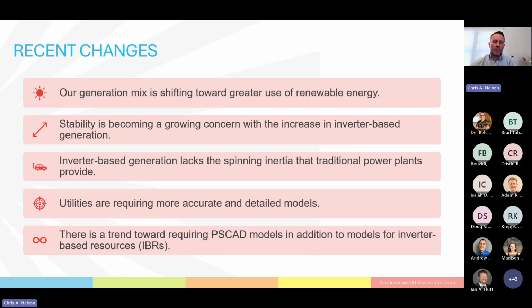So a conventional generator might provide 8 to 10 times the fault current of nominal if there's a problem, and it'll just continue spinning even if there's a little problem. Inverters might not do that, they just don't have the inertia behind them. We've seen problems with relay settings as well, but they're doing the best they can to work around that. Either way, utilities are requiring a lot more accurate and detailed models to try to make sense of what's going on and make sure the grid is as stable as they can make it.